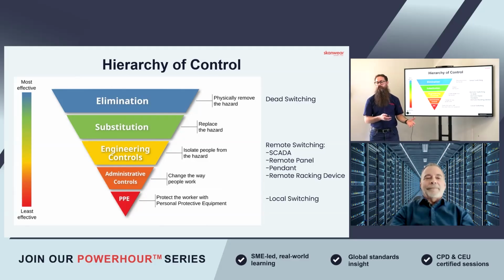And then finally, we're going to look at what PPE requirements we're going to need for the task. If we're switching from remote, we'll have limited interaction with the switchgear, so we might have a reduced requirement for PPE for both shock and arc flash. In this example, we're doing local switching because it's an older network, and we've selected the correct PPE for the fault levels and for the incident energy values on that network.